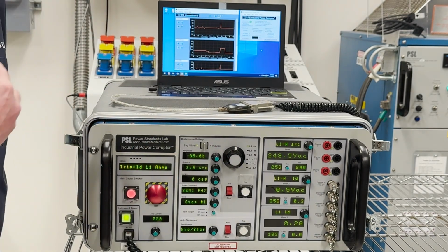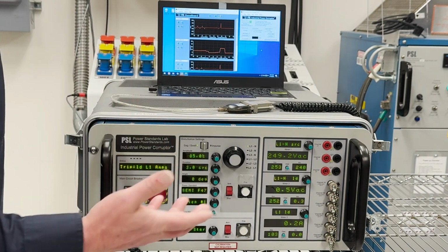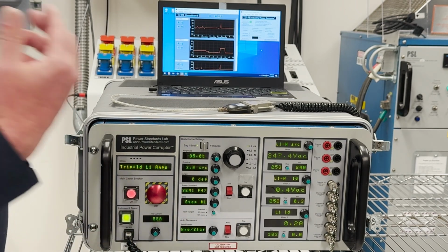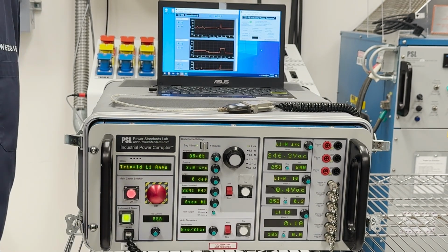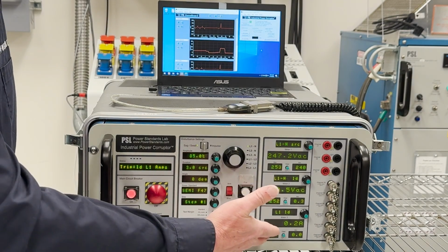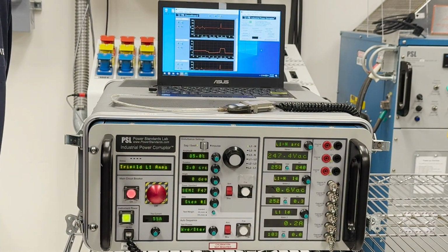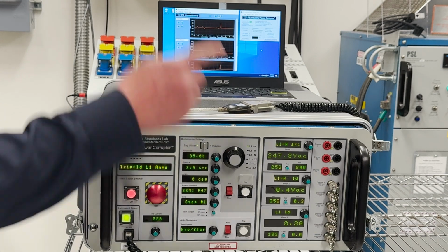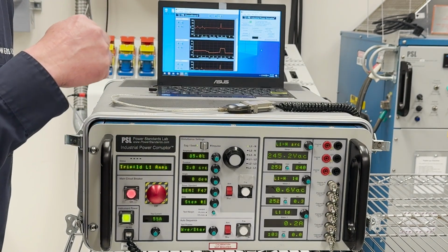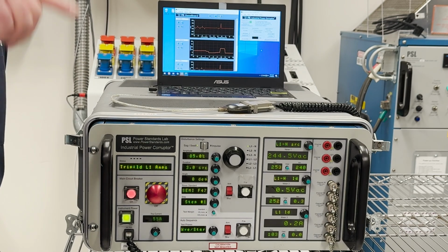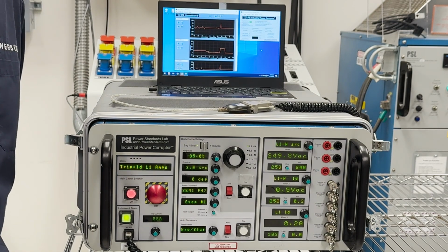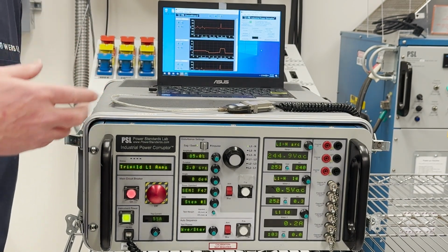So it's protecting your equipment under test, but clearly the current that we expected was higher than the trip setting, and you can see that here immediately. You can see over 100 amps pull as the maximum, even on this relatively slow voltage meter. By downloading on channel scope, you can also look at the specific characteristics and look at the curve shape and see what the peak was that occurred because of this capacitive load.